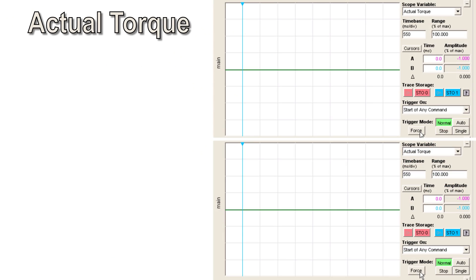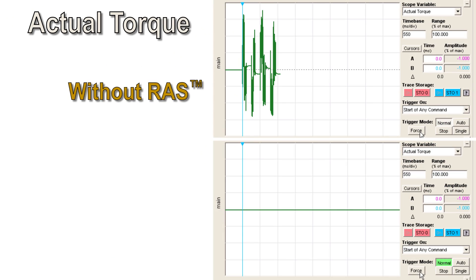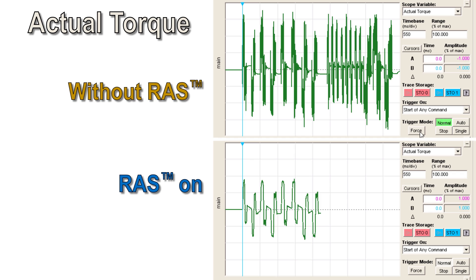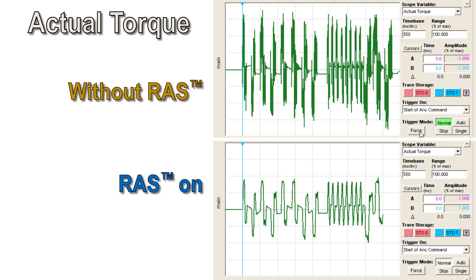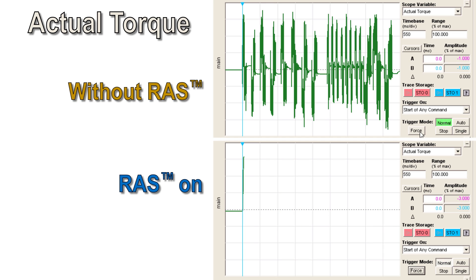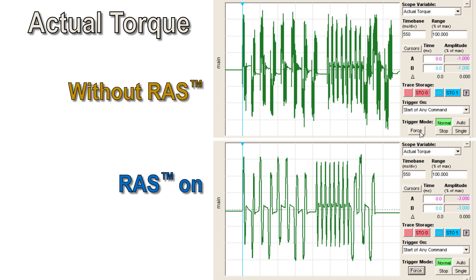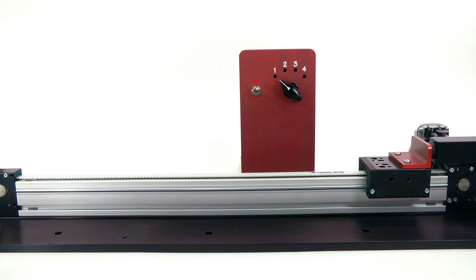Now let's add some RAS. Here's what the torque looks like with the RAS off... and with the RAS on. With the RAS on, the torque has none of the spikes that you get from the sharp transitions of a trapezoidal or triangular profile. This allows you to set the acceleration much higher and still get smooth motion. The scope now shows the torque with moves at twice the acceleration — the moves are smoother and faster than without the RAS.